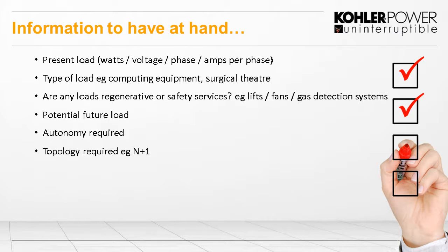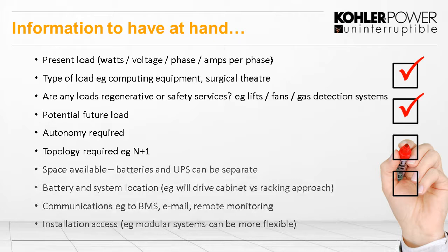Obviously, the present load might not be the future load. The load might go up or down, and of course, we need to plan for that during the design. And the other important factor is autonomy: how long do you want it to run on battery on a mains outage? You then decide how critical this is. So what topology do you require? Is it N+1 or N+N, or 2N+1, to keep the resilience that you require?